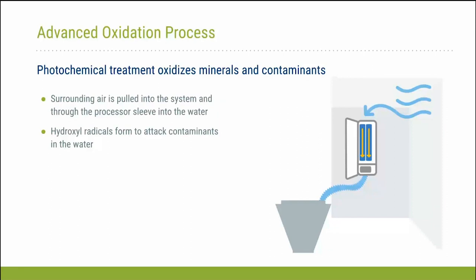So again, an interesting technology, I would say probably one of the lower risk ones to install, given that you can operate the system as normal and then go through that process Todd described of adjusting some of your cycles of concentration set points. You can go through and adjust the amount of chemicals being used, doing that in a way that's systematically deployed to make sure it's operating how you want it to.